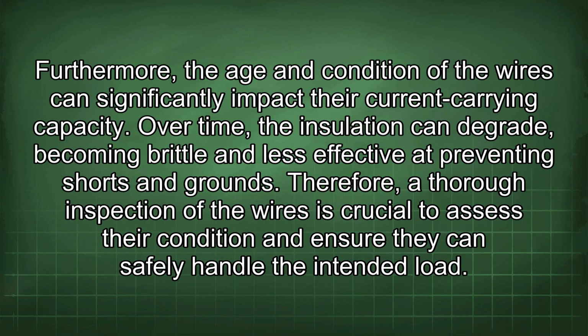Furthermore, the age and condition of the wires can significantly impact their current carrying capacity. Over time, the insulation can degrade, becoming brittle and less effective at preventing shorts and grounds. Therefore, a thorough inspection of the wires is crucial to assess their condition and ensure they can safely handle the intended load.